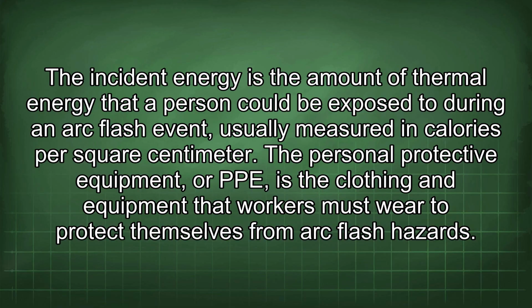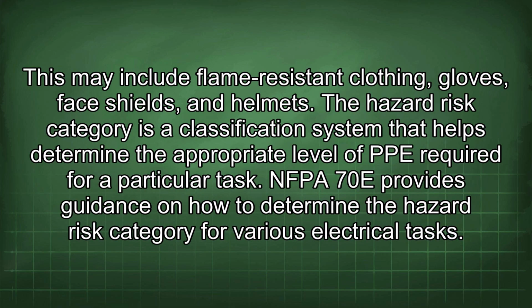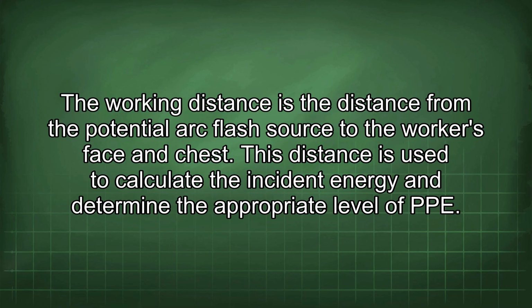The personal protective equipment, or PPE, is the clothing and equipment that workers must wear to protect themselves from arc flash hazards. This may include flame-resistant clothing, gloves, face shields, and helmets. The hazard risk category is a classification system that helps determine the appropriate level of PPE required for a particular task. NFPA 70E provides guidance on how to determine the hazard risk category for various electrical tasks. The working distance is the distance from the potential arc flash source to the worker's face and chest. This distance is used to calculate the incident energy and determine the appropriate level of PPE.